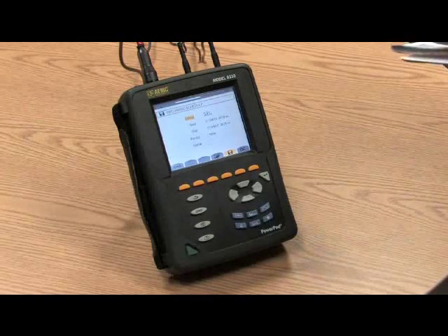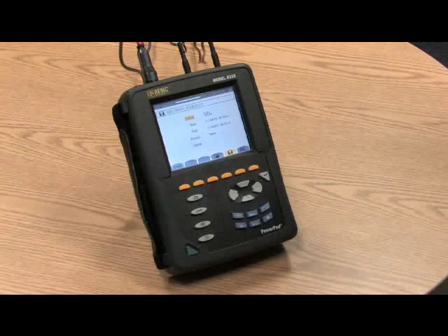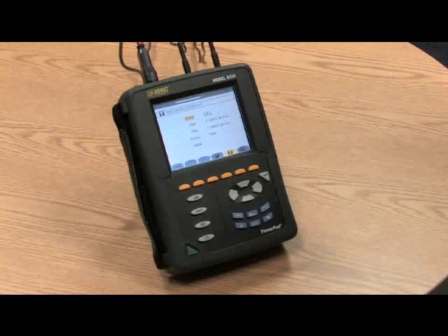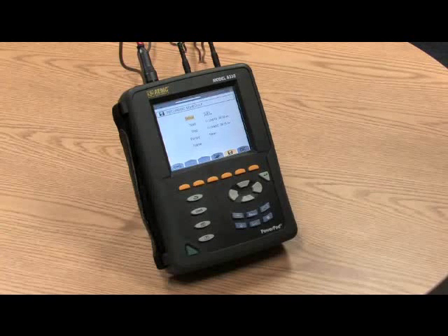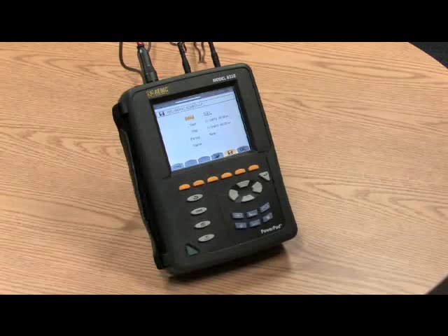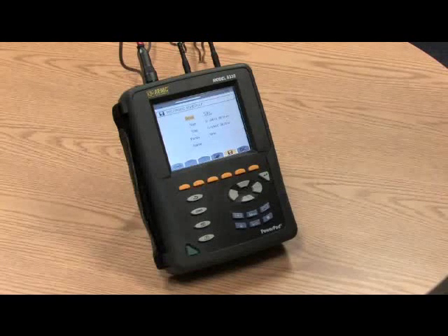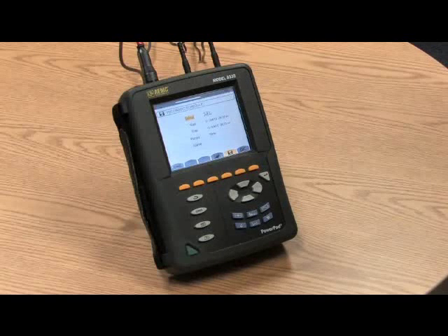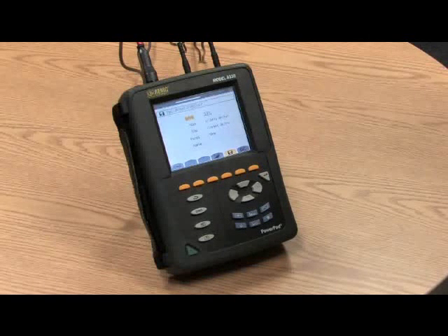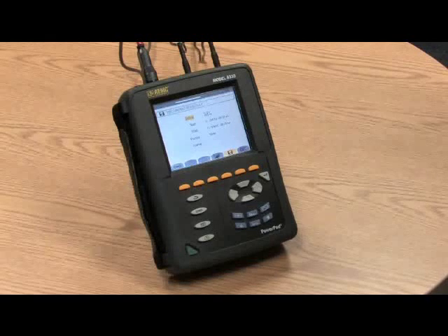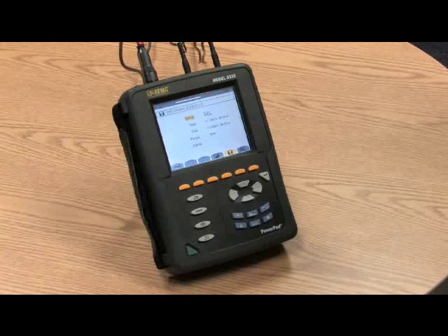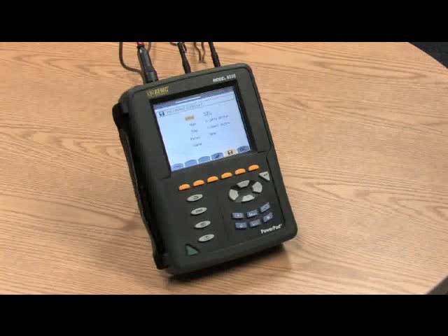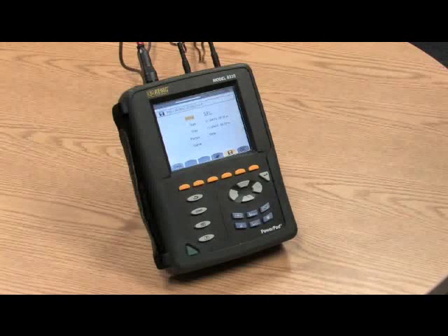Some of the key specifications on the 8335, it'll measure true RMS voltage and true RMS current. It'll measure up to 1,000 volts, phase to phase, or phase to neutral. The current measurement is dependent upon the probe that's connected to it, and we'll talk about the probes in a little bit. And it can be for as low as a few hundred milliamps to as high as 6,500 amps.